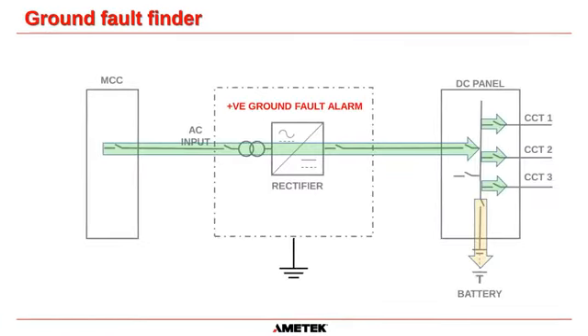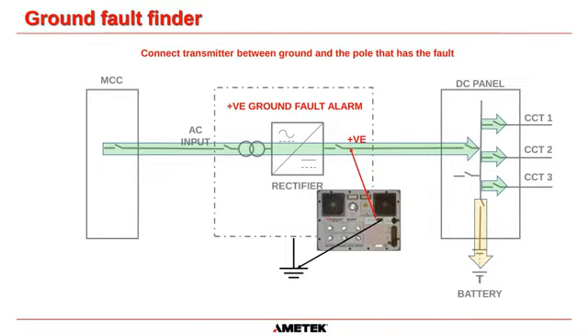What that does is you connect the signal generator. First of all, you have to detect whether the system has a positive ground fault or a negative ground fault. So we're saying we have a positive ground fault alarm. What we then do is connect the signal generator part of the BGFT, the red lead to the positive of the system, and then the other lead to the ground of the system. The signal generator sends a signal only down the path where the ground fault is. So it's sending a high frequency, low current signal down the fault path.